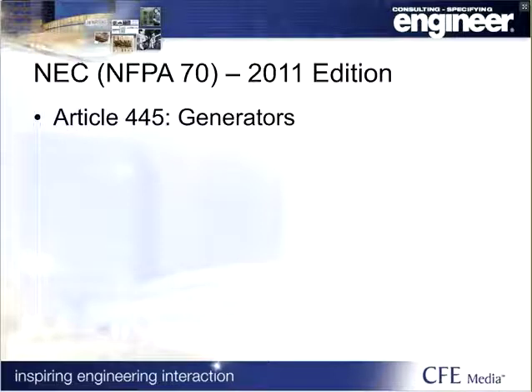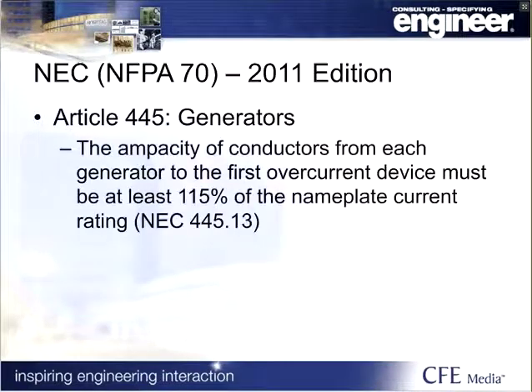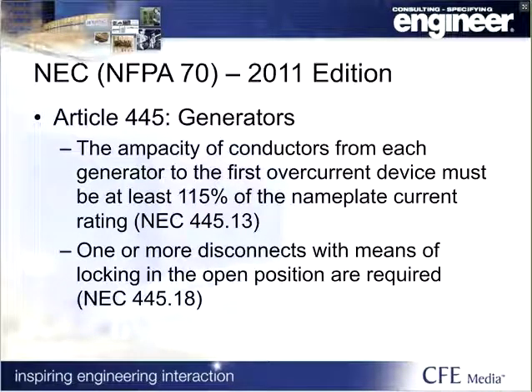NEC Article 445 covers the installation of generators and other requirements. 445.13 provides ampacity requirements for the conductors between the generator and the first overcurrent device. When the generator is provided with an onboard circuit breaker, the conductors are part of the factory wiring. But if the circuit breaker is located remotely, the conductors must be sized for at least 115% of the generator nameplate rating. All generators require a means to disconnect from the load supplied. 445.18 requires disconnects lockable in the open position. Alternatively, the e-stop can serve this function as long as the generator is not configured in parallel with other generators.